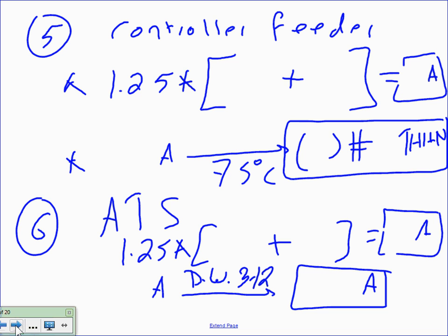Controller feeder. The controller feeder, Chris, my friend, where am I here? You're going to take the full load amps of the fire pump and the jockey pump. You're going to add them up and go 64. I can't emphasize, first you add them, then you multiply by 1.25. That's different than what we did for typical motors. Typically, we take the fattest, fluffiest amp-wise motor, multiply by 1.25, then we add all the other full load current to it. Here, we have to add them and then multiply. That makes the parentheses that everybody can see. When you do that, you're going to end up with 64 amps.